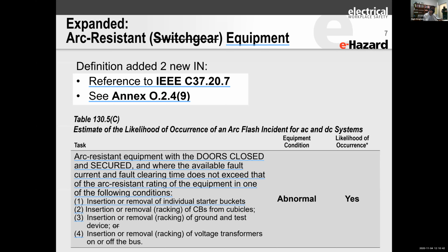Well, when you looked at arc-resistant equipment, initially when it was first launched, it was predominantly for medium voltage or the higher voltage equipment. But as time progressed, we realized that, hey, we can bring this technology down to lower voltages, 480 volt systems. So now what you see is motor control centers, which previously didn't have any sort of arc resistant protection. Now you get motor control centers which are actually arc resistant. What that means, if an arc flash has to occur within a bucket, it basically will channel that energy out to a safer area and vent it out to an area which is not populated by the worker. Okay, so into a safe area.